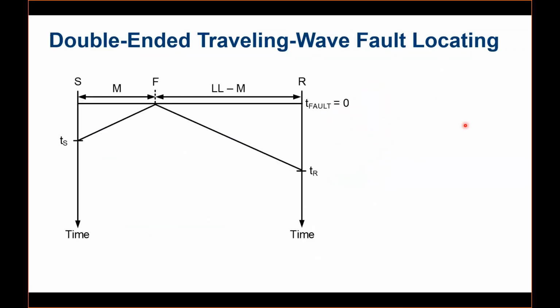Another method is much more reliable. It's called double-ended traveling wave fault location, in which we use the time at which the traveling wave strikes at station S, and also the information from the remote end. So these relays should exchange data on when they have seen the first traveling wave. For example, the traveling wave has been intercepted at station S at time TS, and at the remote end at time TR. If the remote end gives the information to the local end that it has seen the fault at time TR, then using that information the local end can find out the distance M, which is the distance from your point S to the actual fault.